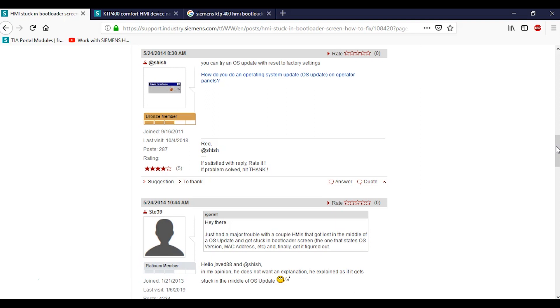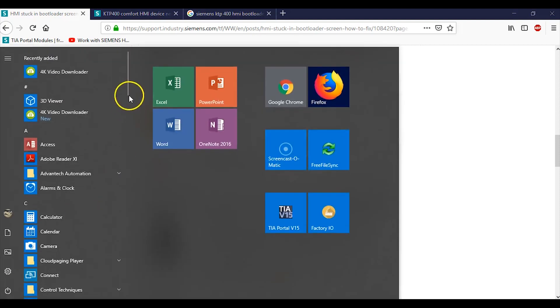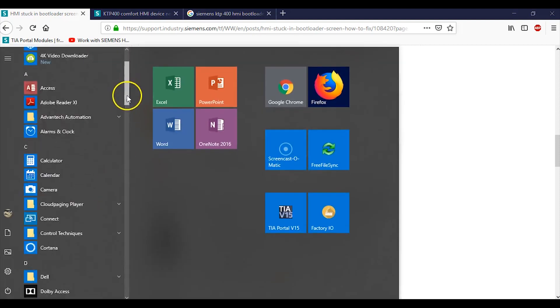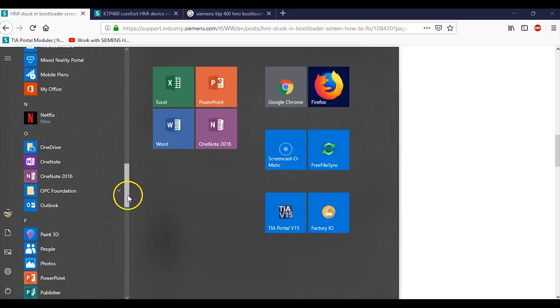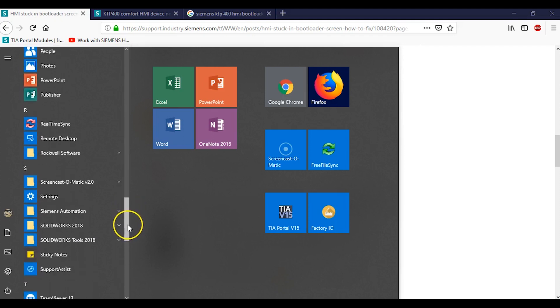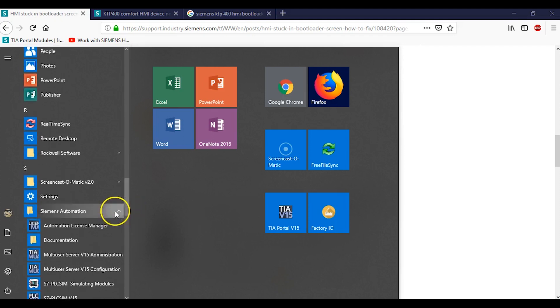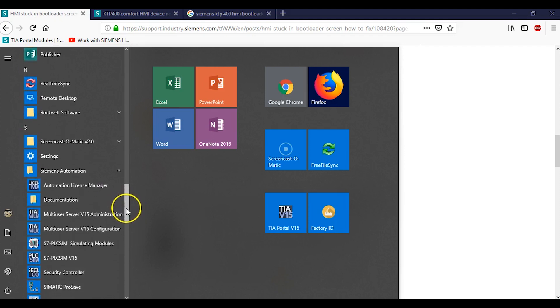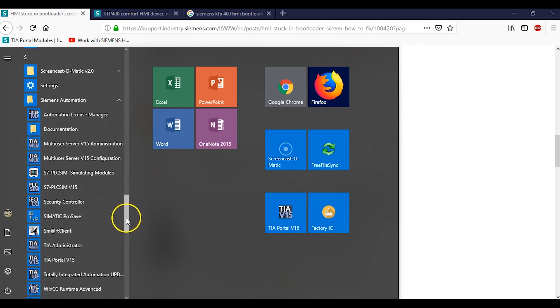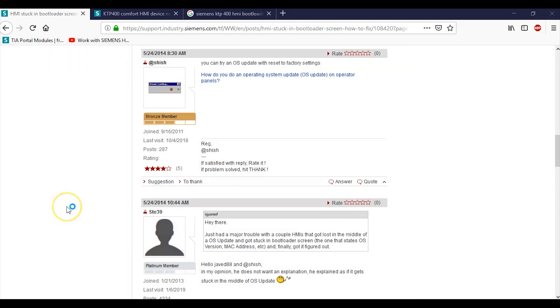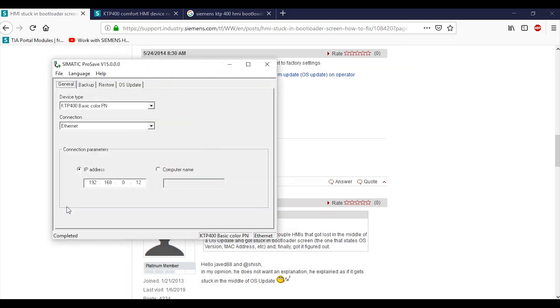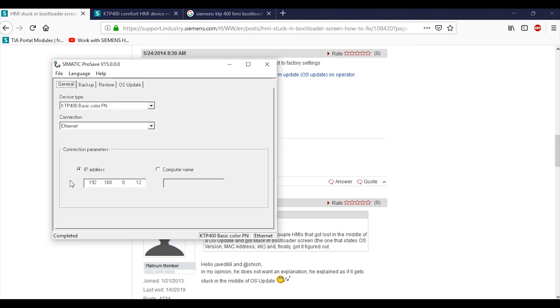So they were saying in this thing to try an OS update and reset to factory settings. I tried that but I wasn't able to talk to my HMI. You can go to Siemens - if we open this guy up, there is this thing called Simatic ProSave. You can talk to your HMI through the ethernet if you still have the ability to talk to it, whether it kept that IP or not. You could also do an OS update. I tried to do that and put the MAC address in, but again I wasn't able to talk to it whatsoever. There was no way for my laptop to talk to my HMI to change anything.